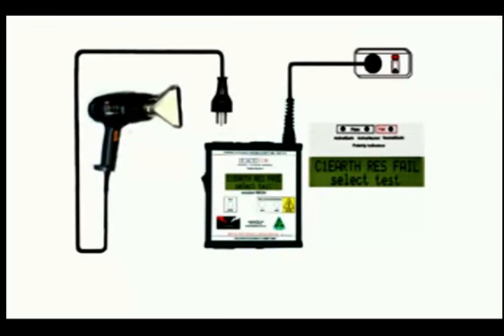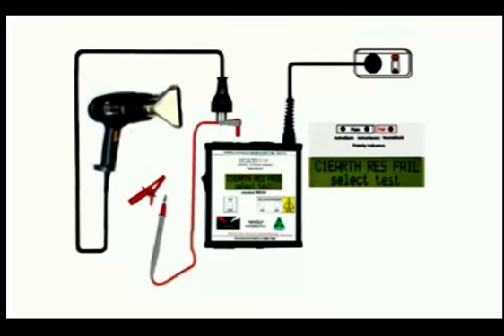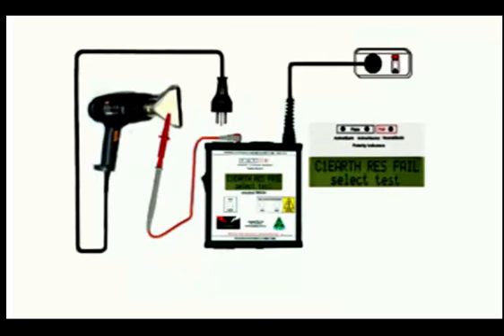We're going to test a double insulated, that's Class 2 appliance, in this case a heat gun. In fact, the procedure is exactly the same whether it's Class 2 or Class 1. So let's go. Firmly clamp the earth probe onto any exposed metal we can find. Check that the appliance and the Mega are both switched off, and plug in the appliance to the top connections of the Mega for run tests.